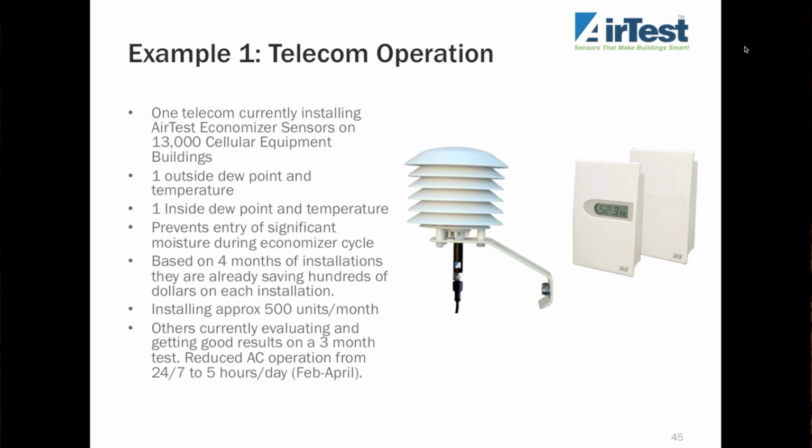In fact, we have others currently evaluating this product and looking at a 3-month period from February to April, they reduced their operation from 24 hours a day to 5 hours a day by effectively using free cooling.